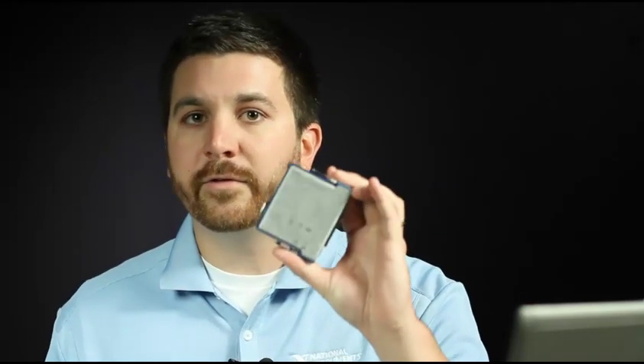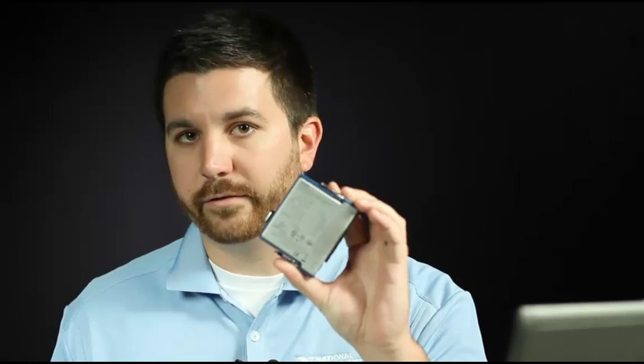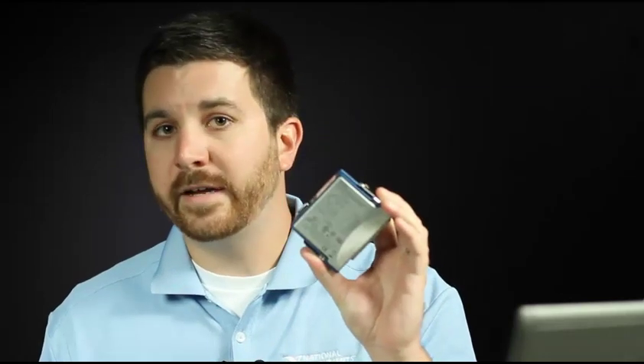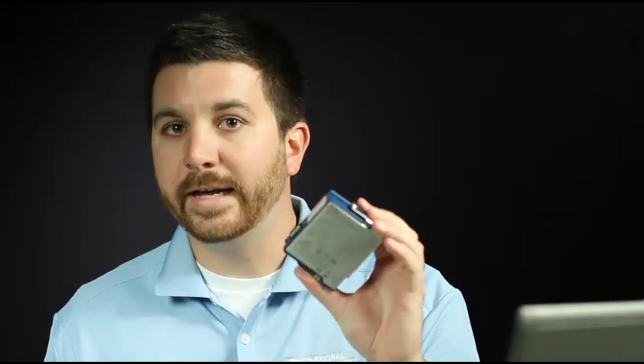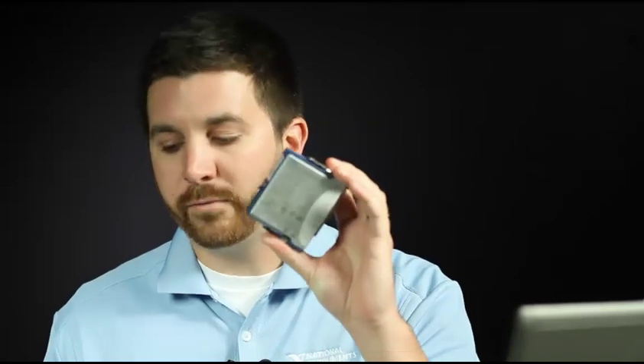So there's a couple things you're going to need to measure a pressure transducer. First, you're going to need to provide it with an excitation voltage. And secondly, since the sensor outputs a signal in the millivolt range, you're going to need some sort of signal conditioning to amplify the signal. And lastly, you're going to need a data acquisition device to measure the signal. In this case, we're going to be using an NI C Series module that's designed for measuring pressure transducers, and it provides the excitation voltage, the signal conditioning, and the data acquisition on this one module.